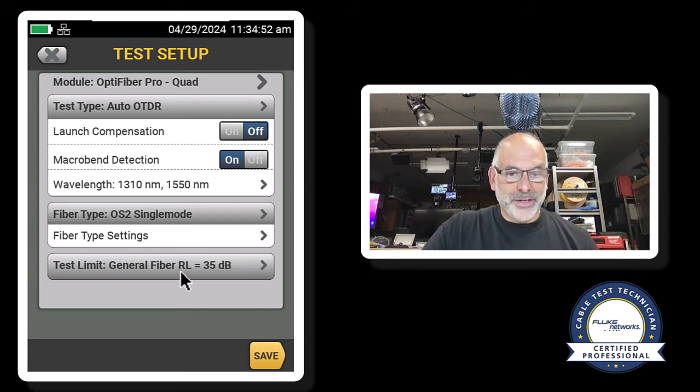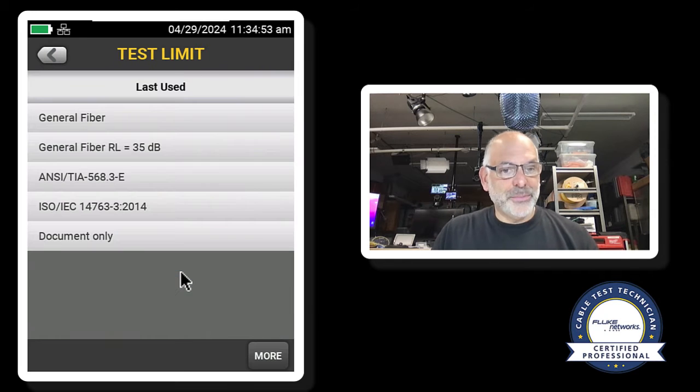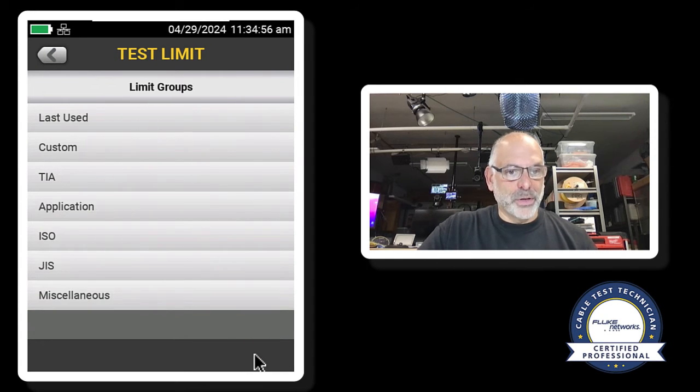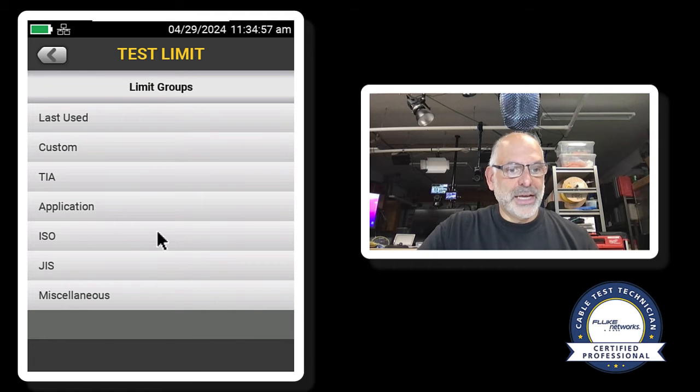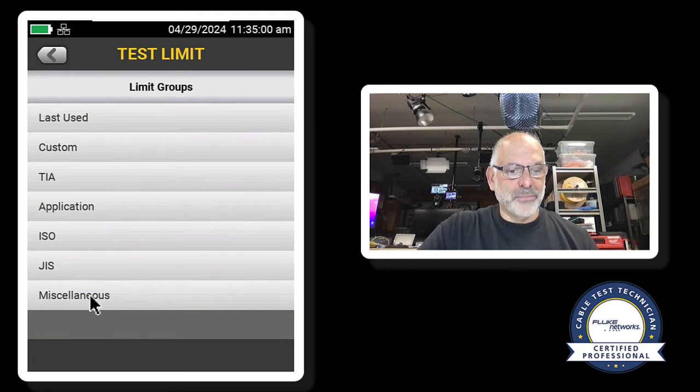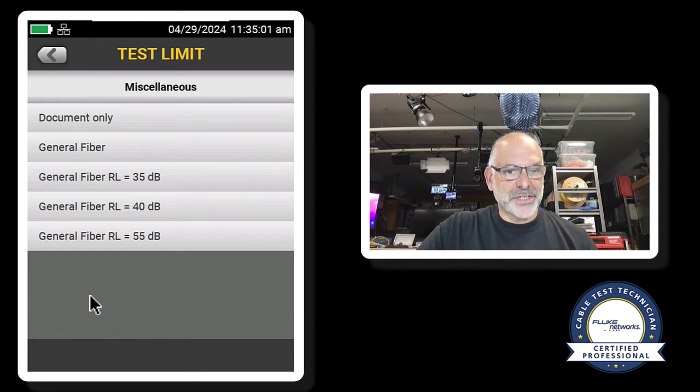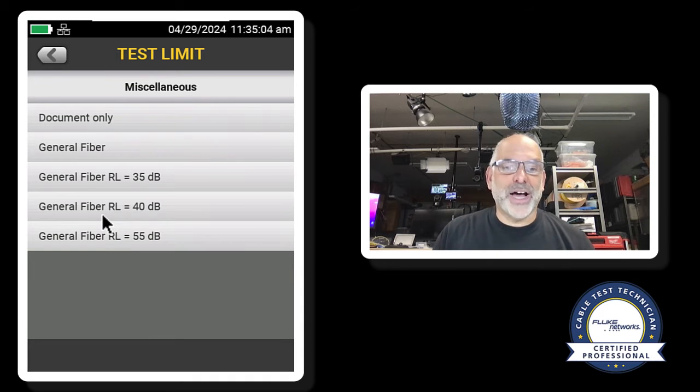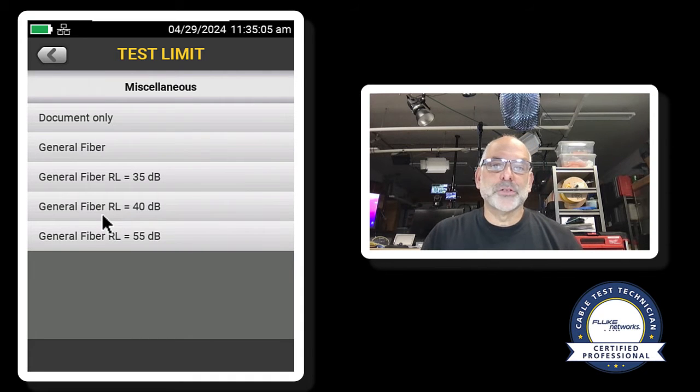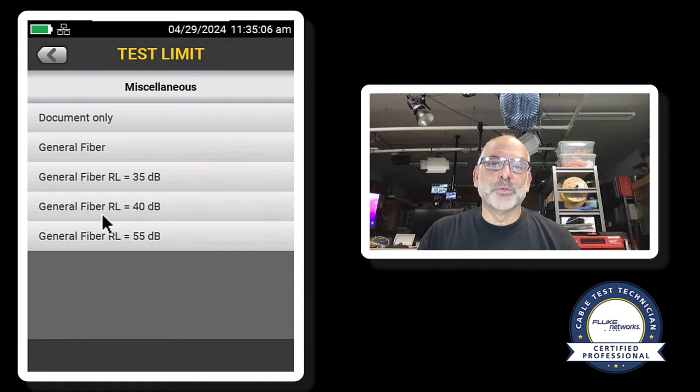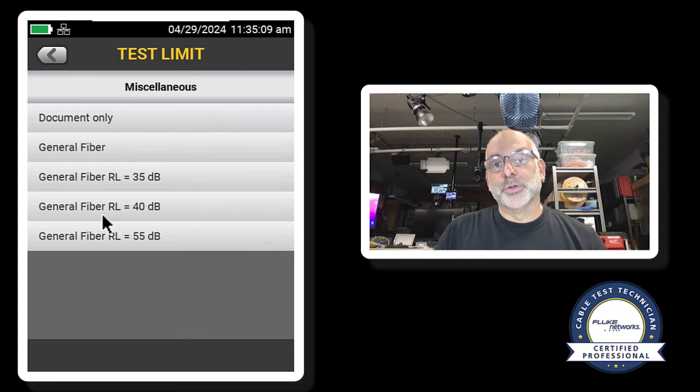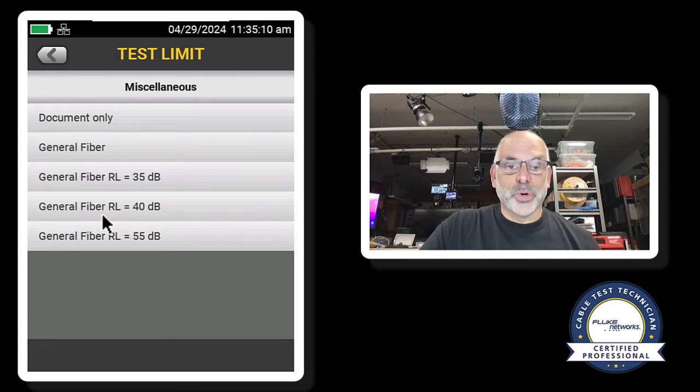And you know what? I'm going to come into my test limit. We're going to go to more, and we're going to go to miscellaneous, and we're going to set our general fiber to a reflectance of less than or equal to negative 40.